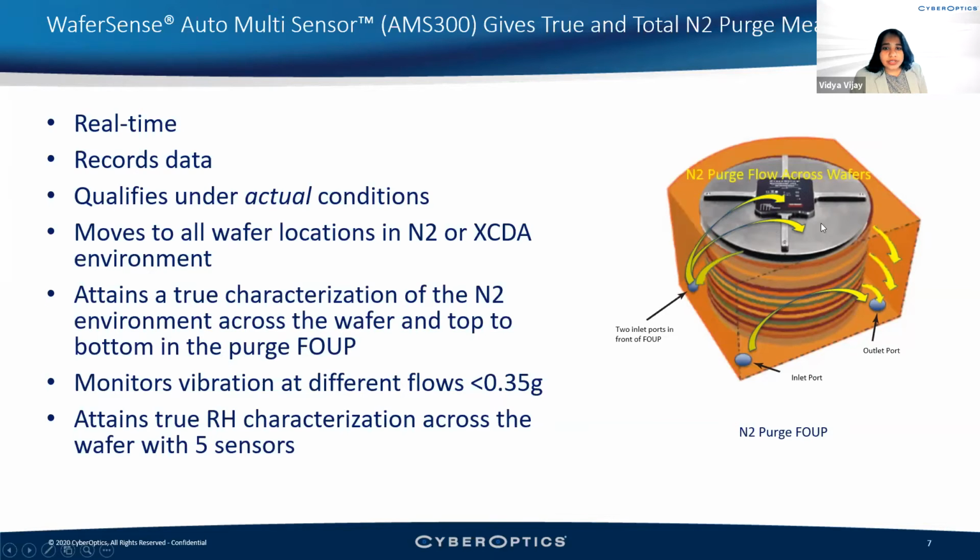So it is important that as it travels, it's communicating in real time. Okay, they are doing a maintenance purge and something is happening. So we are able to see the data in real time, which is very important because they need to know how much to purge and to characterize their maintenance cycle.